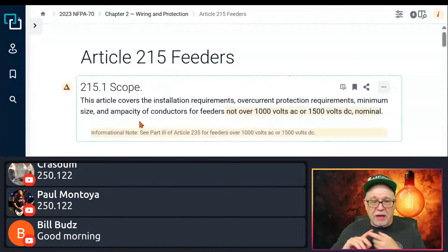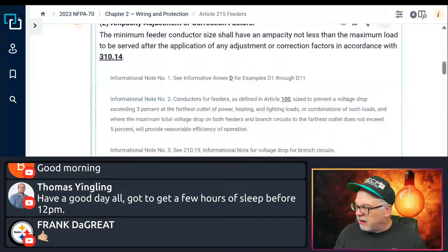All right, so here you go, 215.2(A), minimum sizing. At minimum sizing, and that's what we're talking about, sizing, minimum sizing for feeder. This grounded conductor is part of the circuit, right? So we got minimum sizing here. It says the feeder conductor shall have an ampacity not less than the larger of 215.2A1 or A2, and shall comply with 110.14C, that's terminal temperature limitations. So we're looking down here, and this is A, but B is this grounded conductor. So this is what gives us the direction to go.